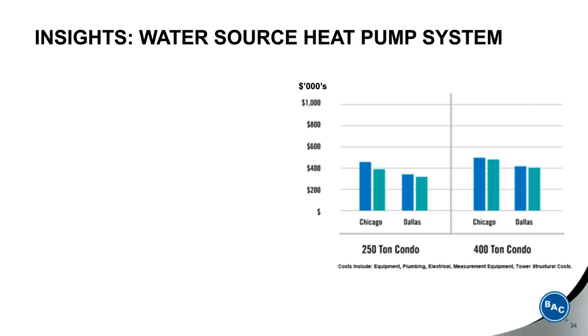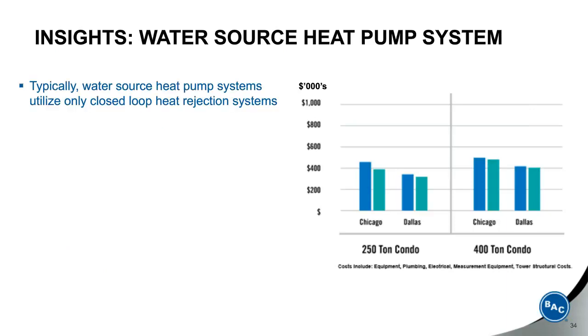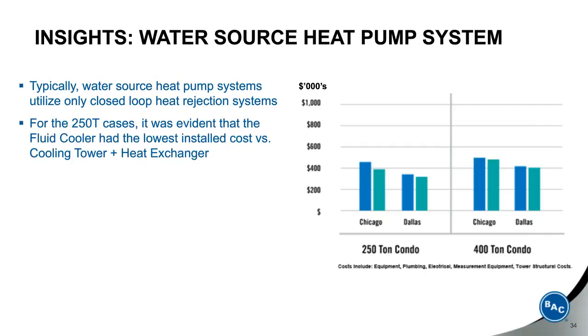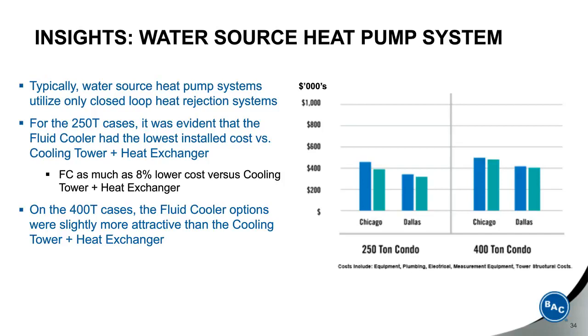So let's look at what we can learn from this part of the study. Typically, water source heat pump systems utilize only closed-loop heat rejection systems. My experience has been that those who use open circuits on these type of systems are usually replacing heat pumps within a year. So keep that in mind. It's not a place to value engineer. For the 250-ton cases, it was evident that the fluid cooler had the lowest installed cost versus cooling tower and heat exchanger. The fluid cooler was as much as 8% lower cost versus the cooling tower heat exchanger option. On the 400-ton cases, the fluid cooler options were slightly more attractive than the cooling tower and heat exchanger.